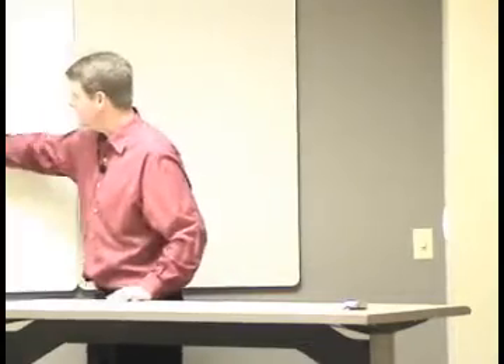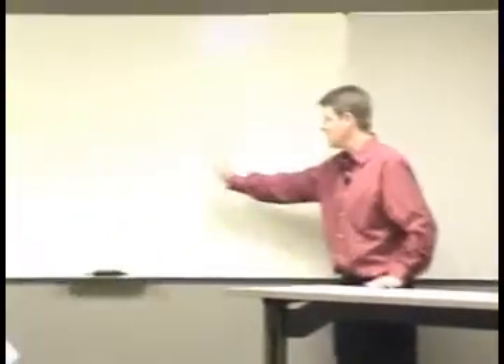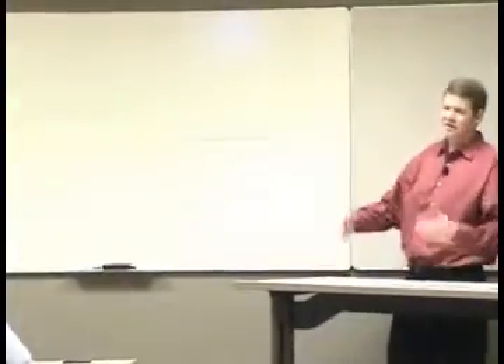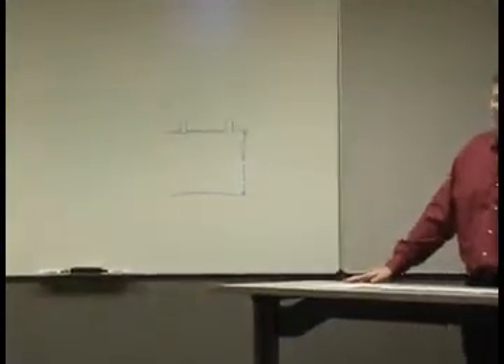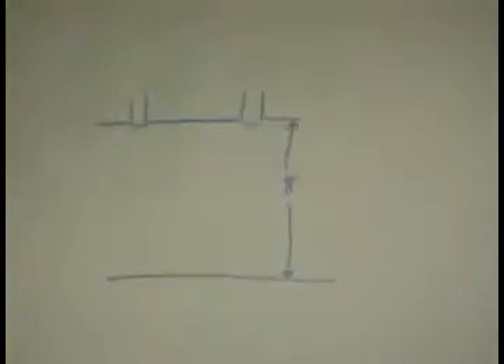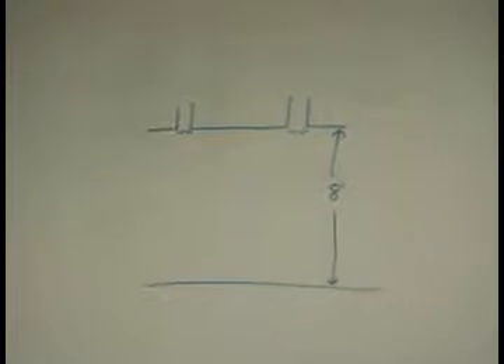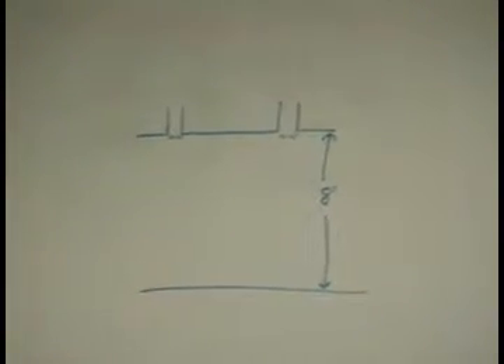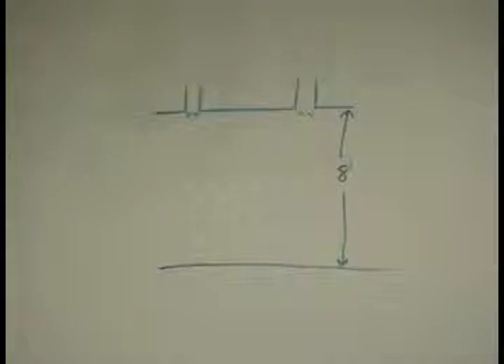Right. So like Mickey is saying, if this is my cross-section of my room, I've got this X number of cubic feet that is losing so many BTUs on a day like this. We got cold going out, or our heat is leaving the building, and we got to get back. We take 1.08 times the difference in temperature times cubic foot per minute and figure out how many BTUs we need to put back in.